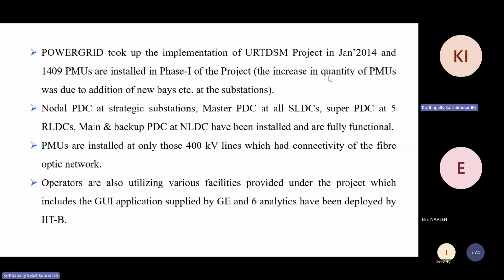As I told, Power Grid implemented this URTDSM project in 2014. 1409 PMUs were installed in phase 1, along with nodal PDCs at strategic substations. For example, if I have 10-20 substations within a nearby 50 kilometer area, I will keep one middle substation as a nodal substation. I will take data from all the nearest PMUs and store it in that nodal substation's PDC, which is why it's called the nodal PDC at a strategic substation. It then sends data to the master PDC at the SLDC, and then to the super PDC. These PDCs, or phasor data concentrators, are servers located at the RLDC, regional load dispatch centers, and state load dispatch centers.